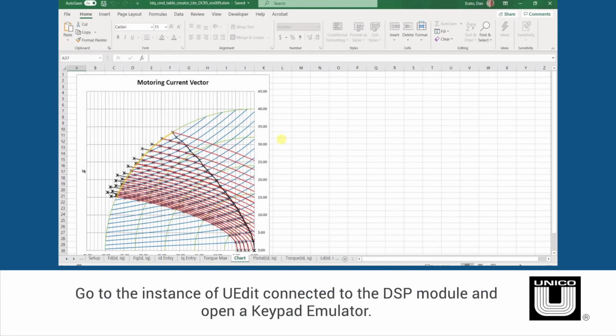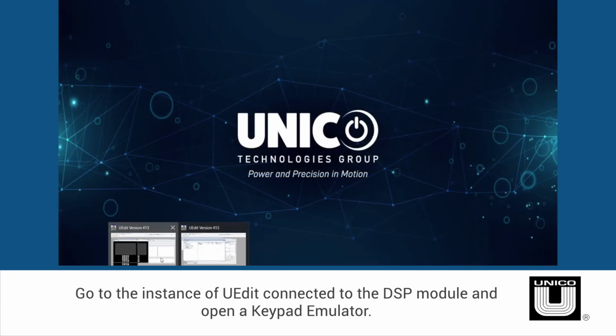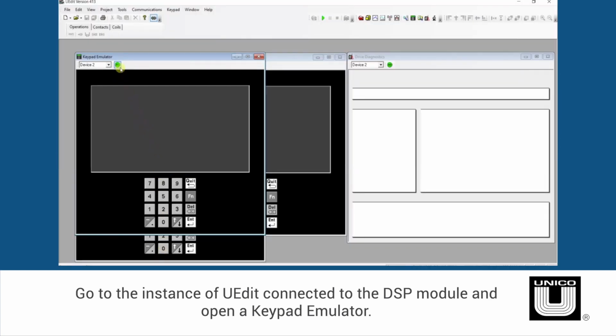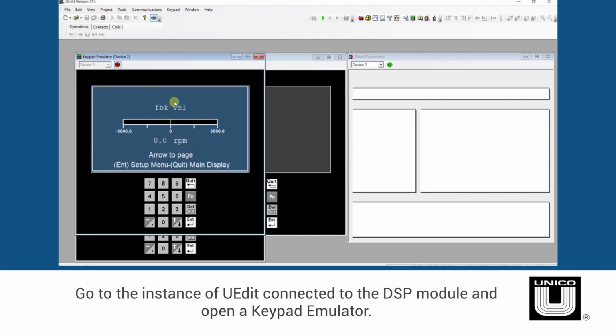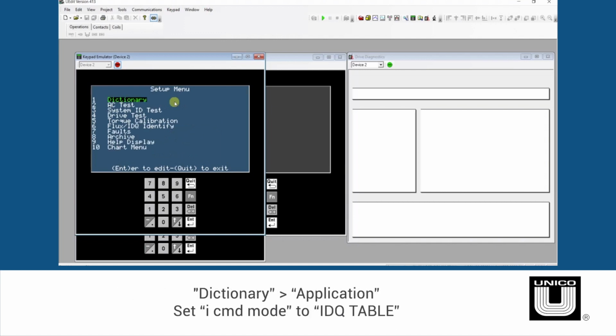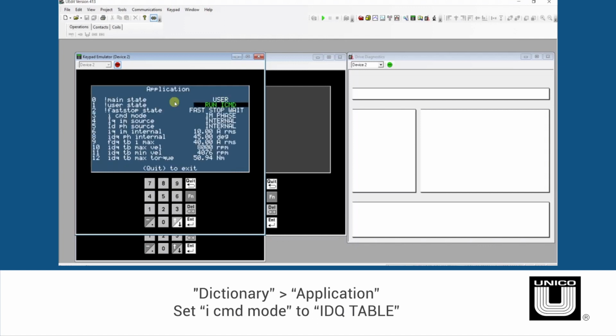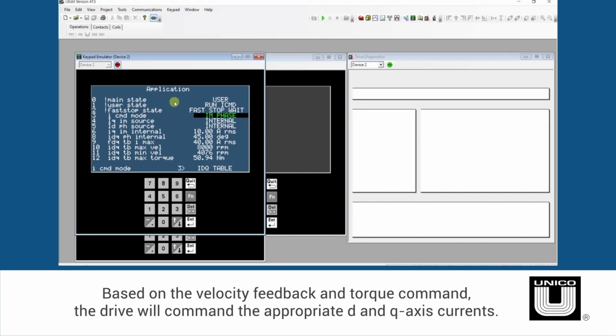The next step is to configure the drive to use the IDQ command tables. So go to the instance of UEdit connected to the DSP module and open a keypad emulator. Go to Dictionary, Application, and set iCommand mode equal to IDQ table. Based on the velocity feedback and torque command, the drive will command the appropriate D and Q axis currents.